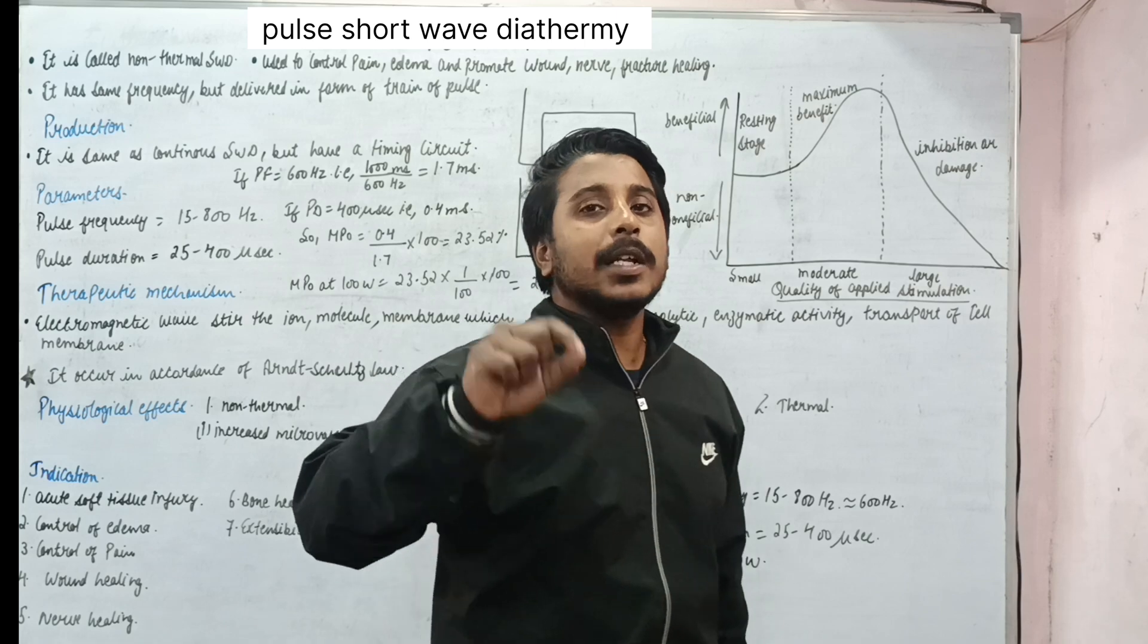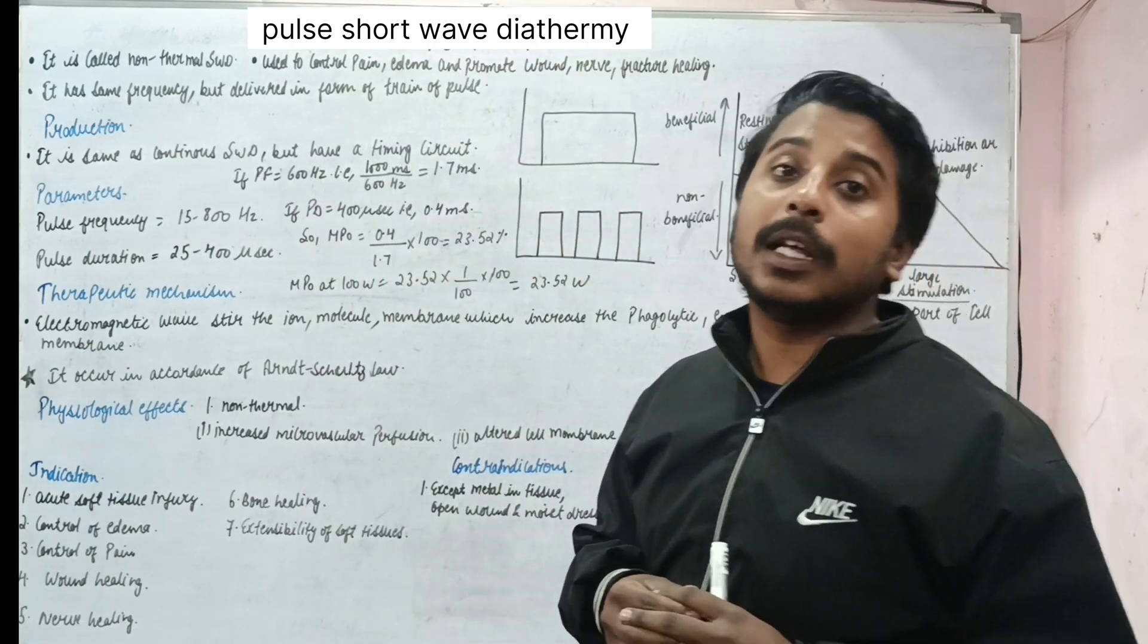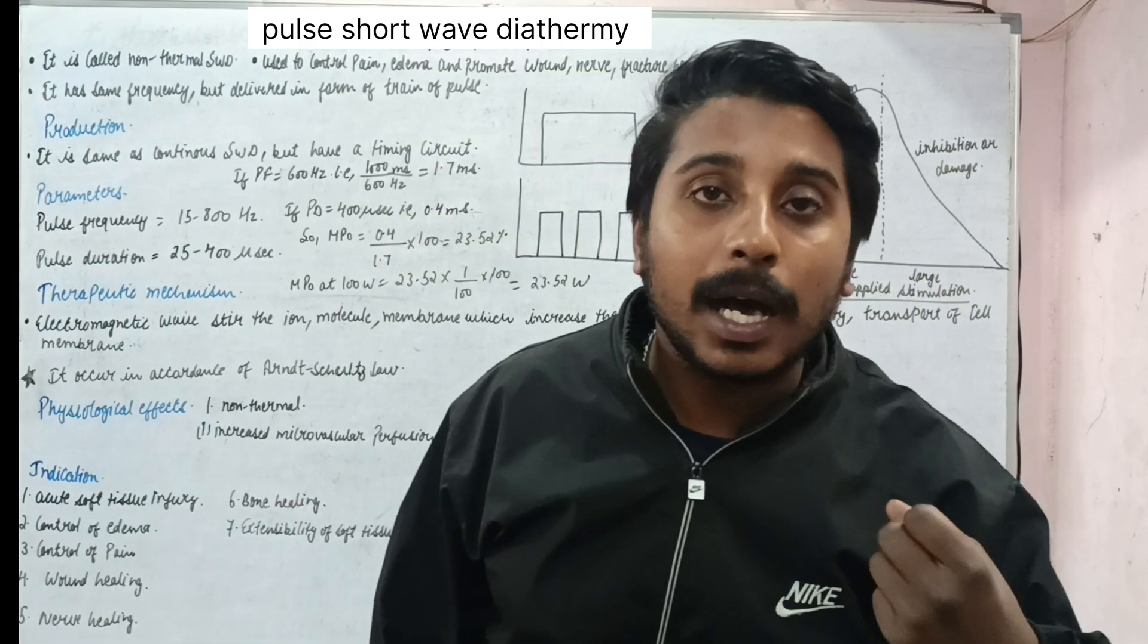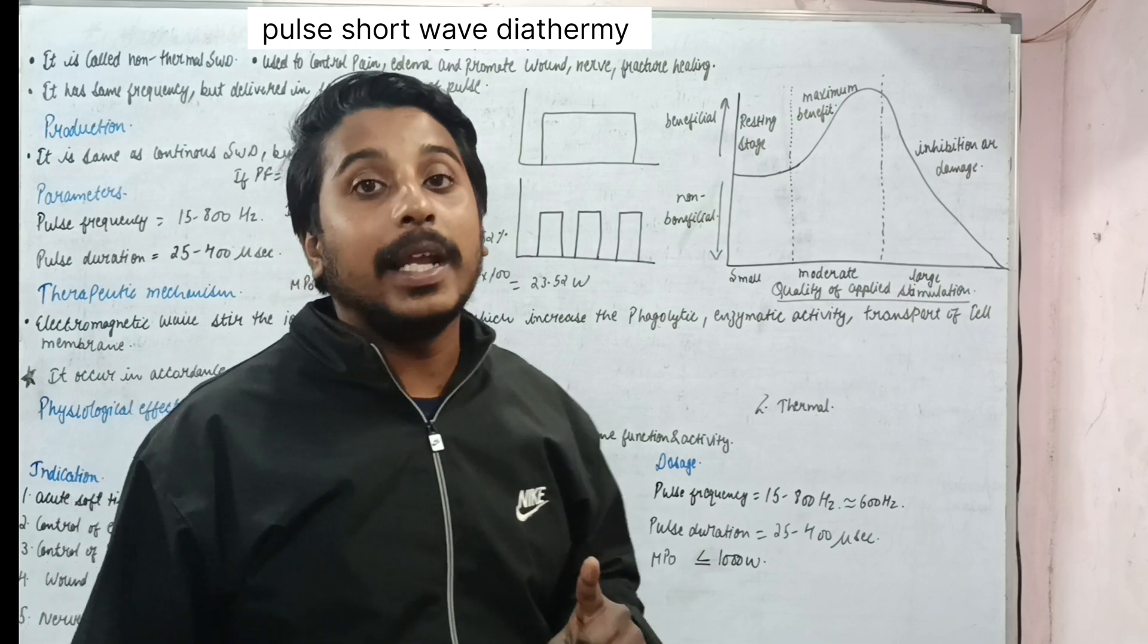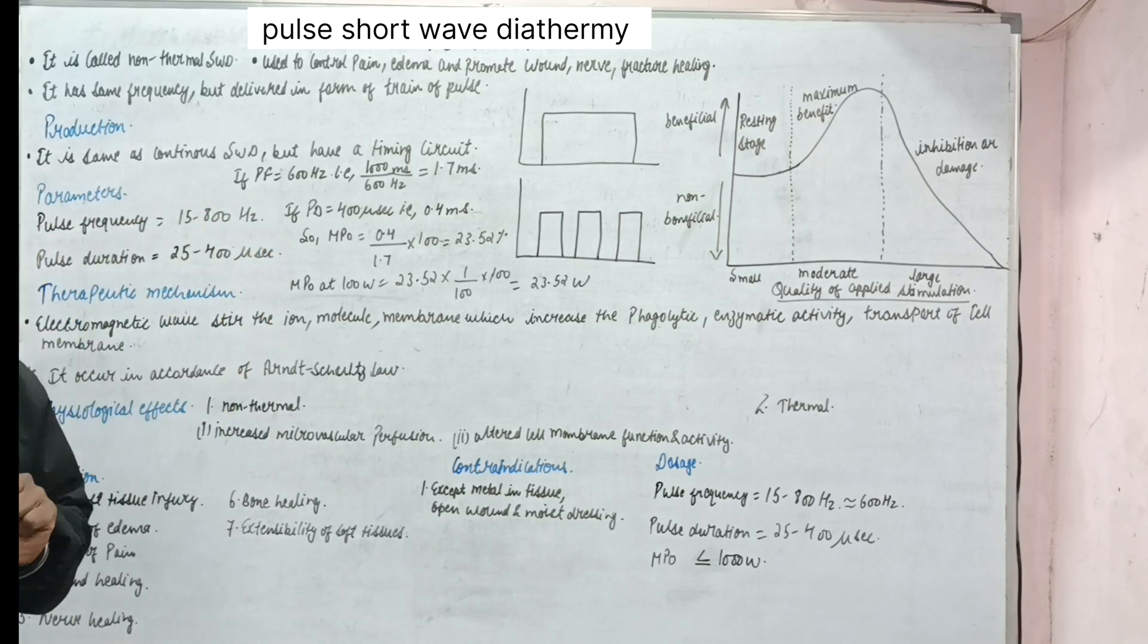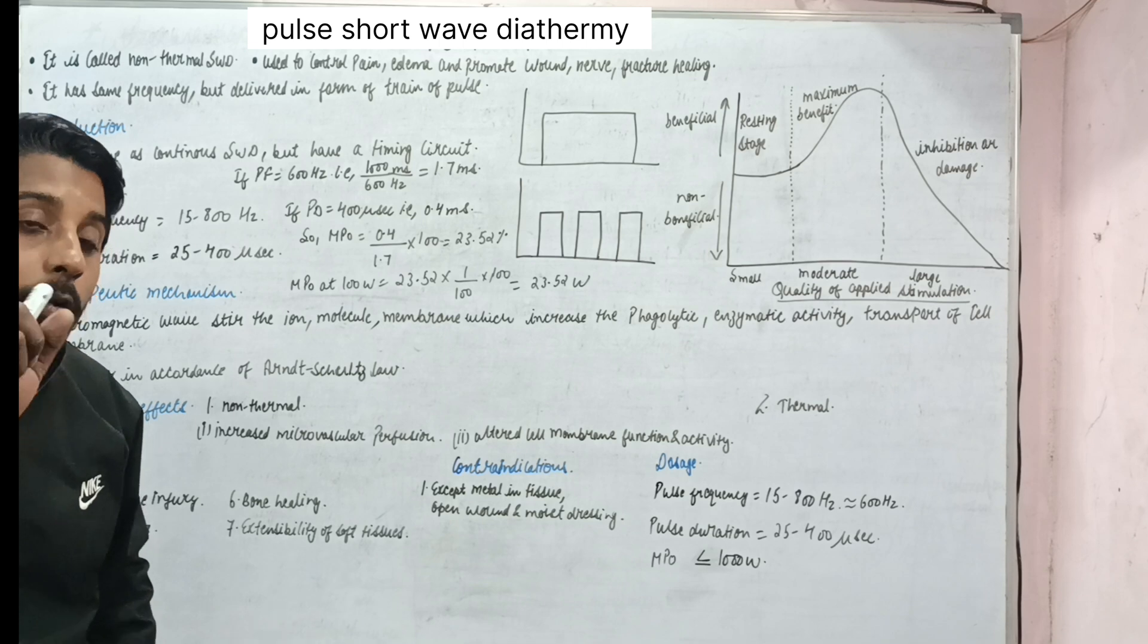So the first question is what was the need of Pulse Short Wave Diathermy? The reason was that after the discovery of Short Wave Diathermy, many studies were conducted in which they used Pulse Short Wave Diathermy and found that in acute condition this was proving to be more beneficial. The continuous form was more used in chronic condition, but for acute, PSWD is used. Why? Because it gives interruption in the emission of Short Wave Diathermy which further reduces the thermal effect, and you know very well that in acute condition we need non-thermal effect. So it proved to be more beneficial than continuous short wave diathermy in acute condition.